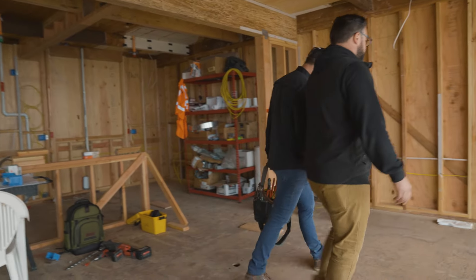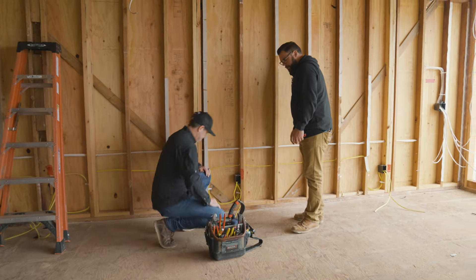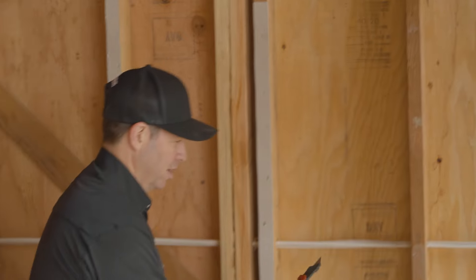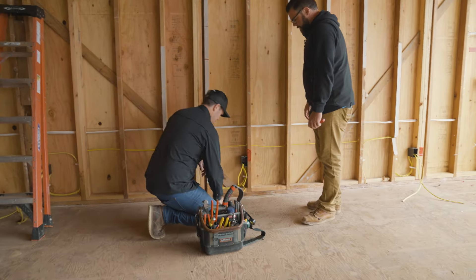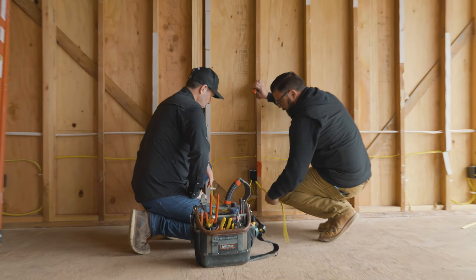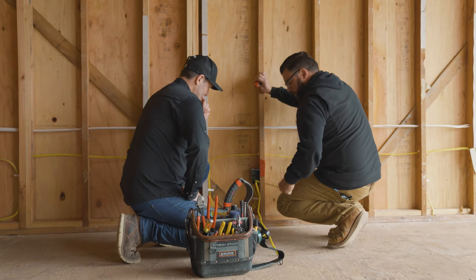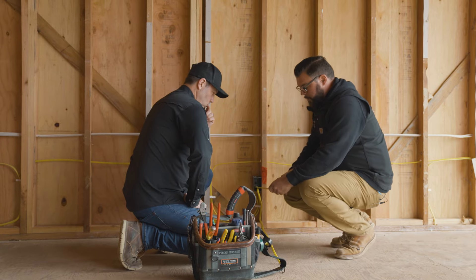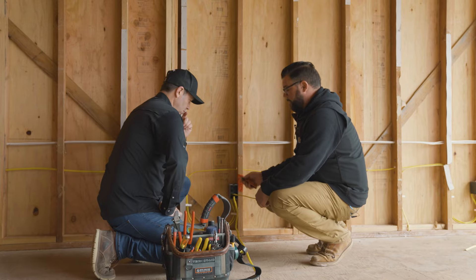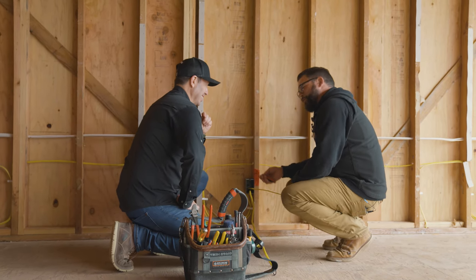So you don't put actual outlets in right now. No receptacles, no switches, no dimmers until trim out. We come back after paint, but we barely have to do anything at that point — we're just connecting the device. Can you show me how to do one? Safety first — we're working with razor knives. Be careful with these kids. So flat and nice is what you want. If you've ever stripped Romex, you want to be right in the center of the wire. Keep your finger and hands away from the blade.